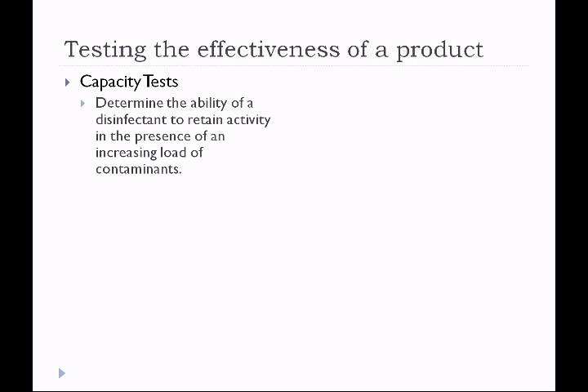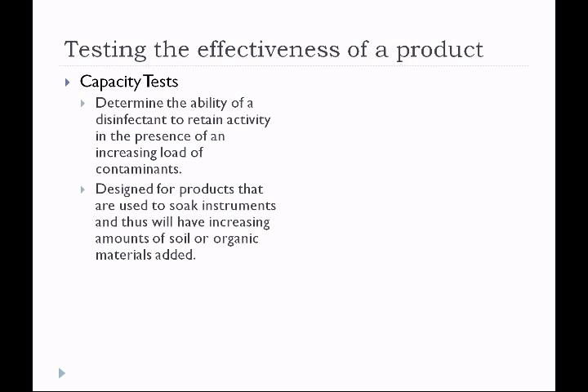Capacity tests determine the ability of a disinfectant to retain activity in the presence of increasing loads of contaminants. These are designed for products used to soak instruments, which accumulate increasing amounts of organic material over time. For example, if medical instruments are added to a container of disinfectant over one or two days, there will be less organic material at the beginning than at the end. This test determines how much contamination load the disinfectant can handle — its capacity.